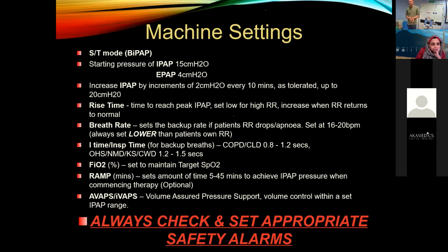National guidelines here are to have that backup rate set at 16 to 20 breaths a minute. The key is this backup breath rate should always be set lower than your patient's actual own respiratory rate. If you have it set higher, the machine is going to start triggering timed backup breaths, and then it will desynchronize with your patient and they'll just become intolerant of the therapy.